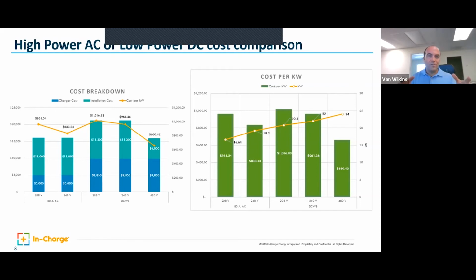Most commercial buildings have a transformer at 480 volt, then step down to 208 for receptacles. But those transformers aren't sized for a bunch of car chargers. I can usually put in one in a commercial building without upgrades, but when I add 3 or 4 ports, now I need a new panel, a new transformer. You bring the voltage in, step it down, take it to the vehicle so the vehicle can bring it back up for its battery. That extra transformer, panel, and bigger wire starts making it not worthwhile.